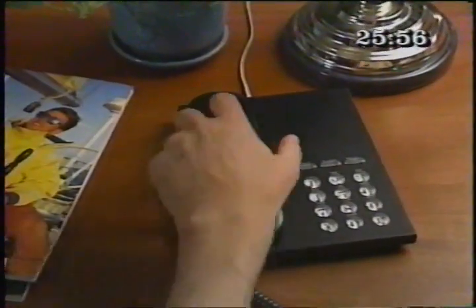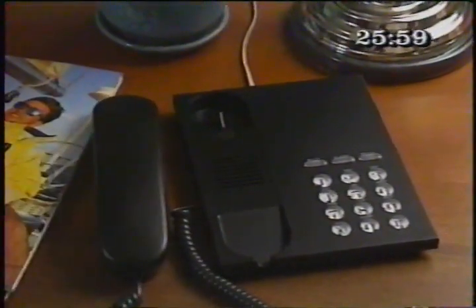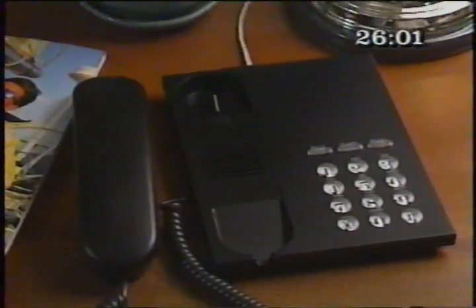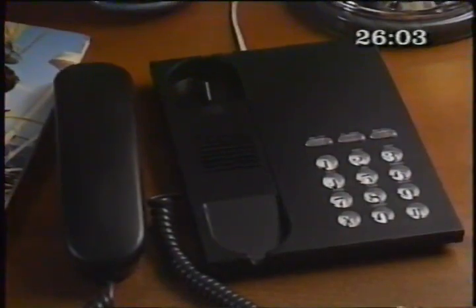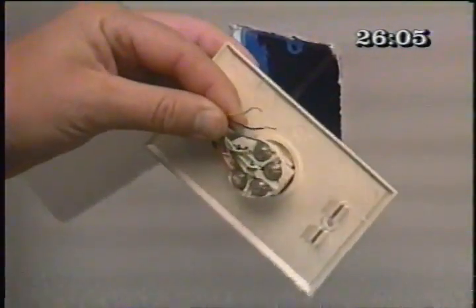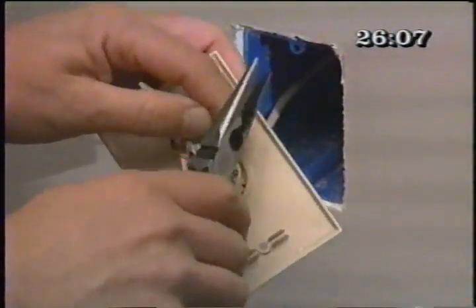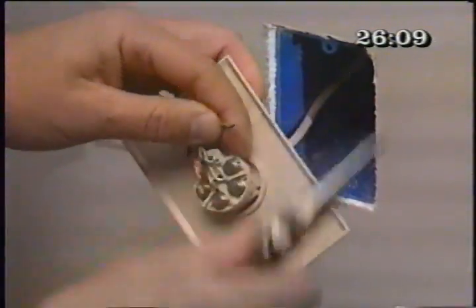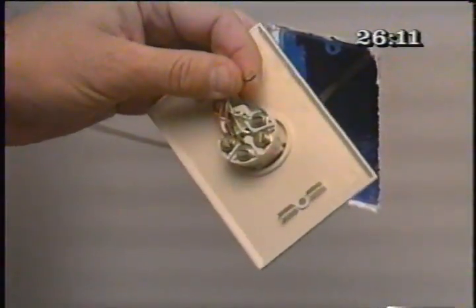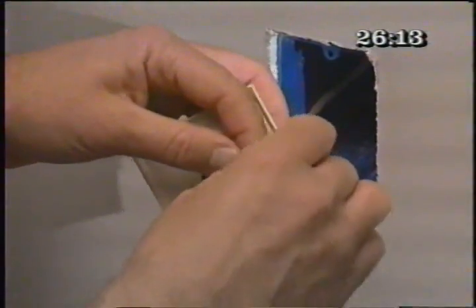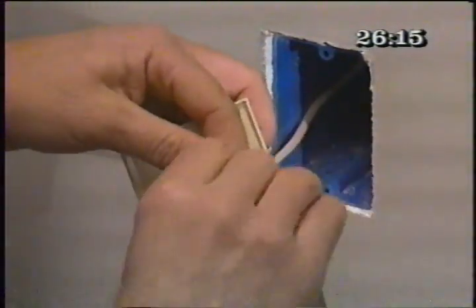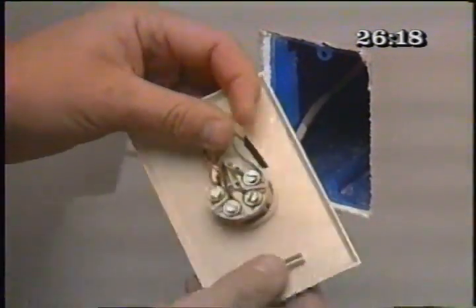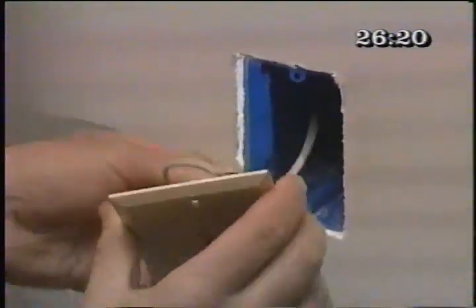Remember, it's wise to take a telephone at another location off the hook if possible to guard against an electrical shock from ringer voltage. If long strands of wire trail off from the screw, clip them back to prevent a short circuit. If there are unused yellow and black wires that have no convenient mounting point, consider trimming them back until the insulation covers all the conductor in the wire, and taping the ends with electrical tape to prevent short circuits.